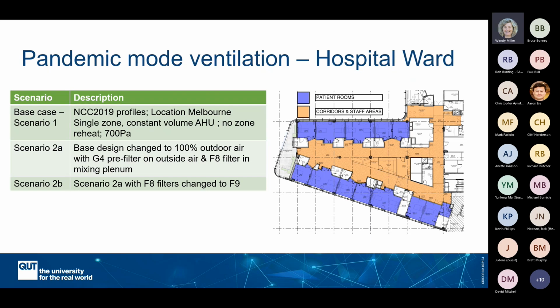Three ventilation strategies were modelled. So the base case, as shown in the first row of the table, is based on the 2019 National Construction Code profiles and uses a single zone constant volume air handling unit, no zone reheat, with the pressures as listed. So this scenario is not representative of the actual ward design for Footscray Hospital, as the mechanical services haven't been fully finalised yet. But this is a fairly common standard way that a ward would be ventilated.